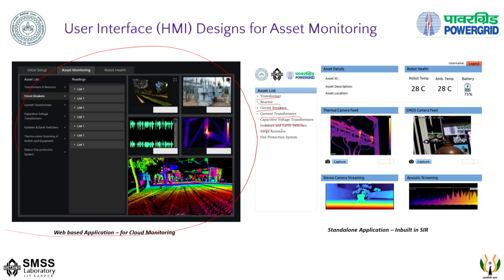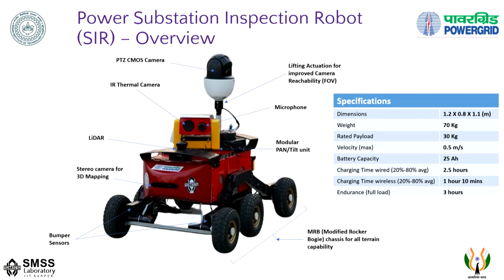So, it is going to talk about whether the robot is going through each one of them or not, and as it is traveling it is going to detect the asset ID, asset description, location, etc., the corresponding thermal camera reading, robot's temperature, ambient temperature, and battery. This you have to always keep track of so that the robot itself is healthy, and then the capturing mode of all the data, and then the stereo camera streaming of the data, and the acoustic reading, as I told you, corresponding to the transformer and the reactor.